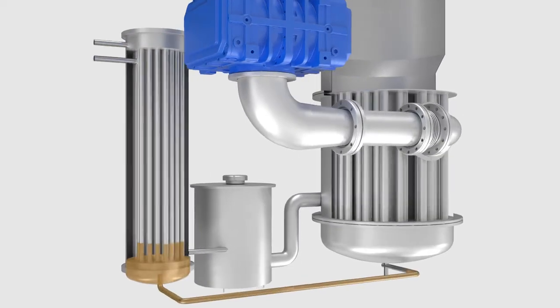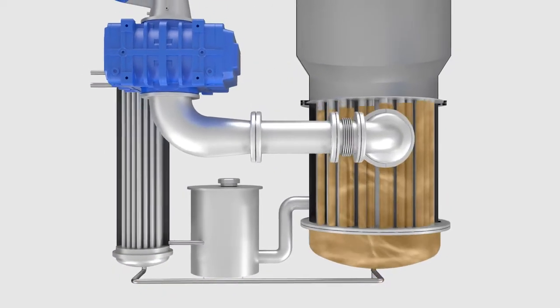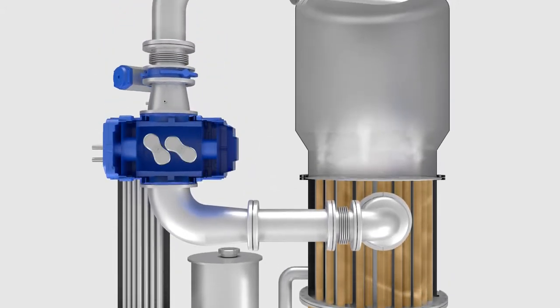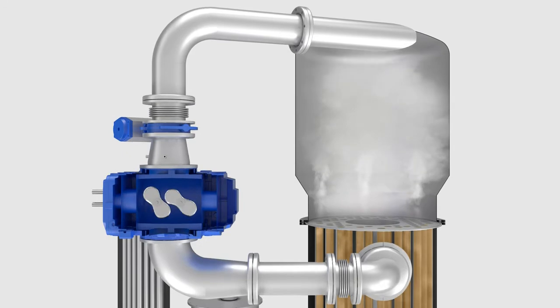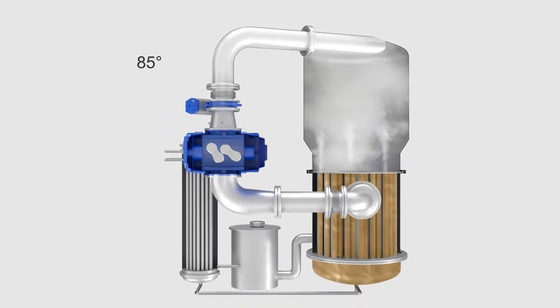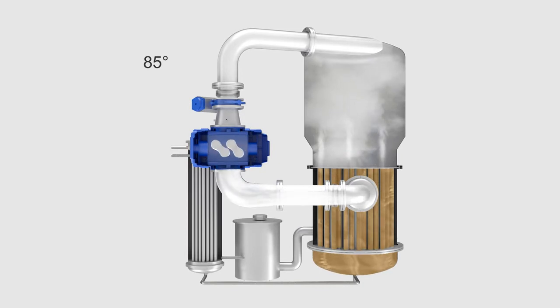At the beginning of the process, industrial wastewater is pumped into the heat exchanger and evaporated under vacuum. The vapor compressor compresses the 85 degree hot steam, creating compression heat. Steam leaves the vapor compressor at a temperature of 120 degrees.